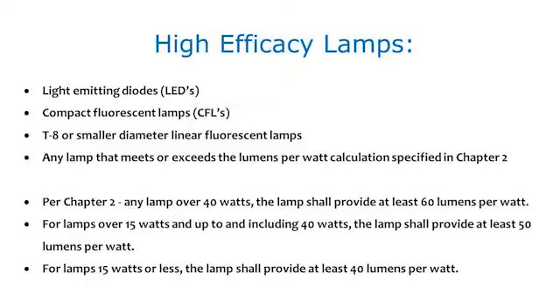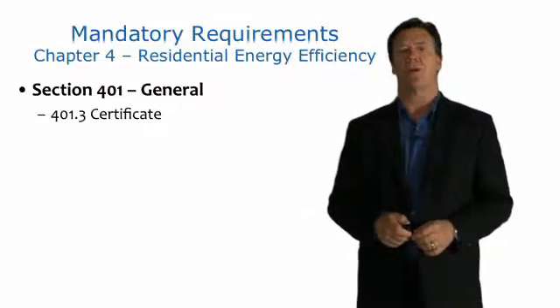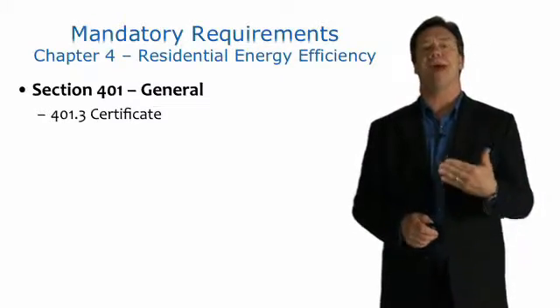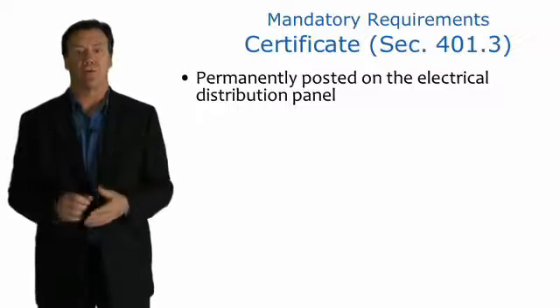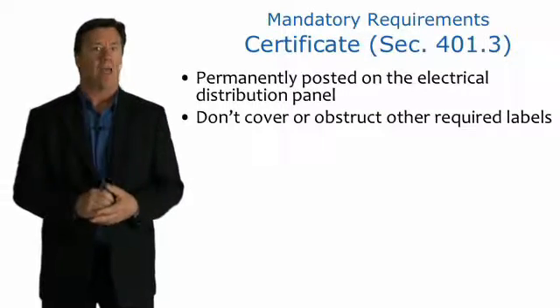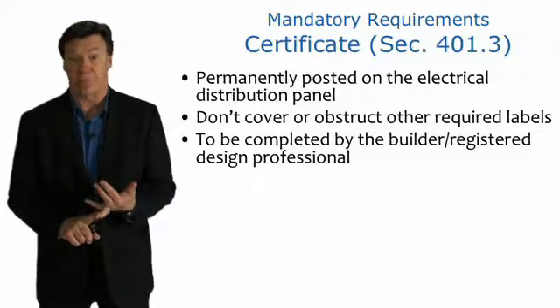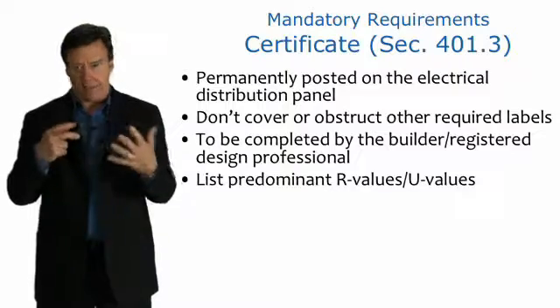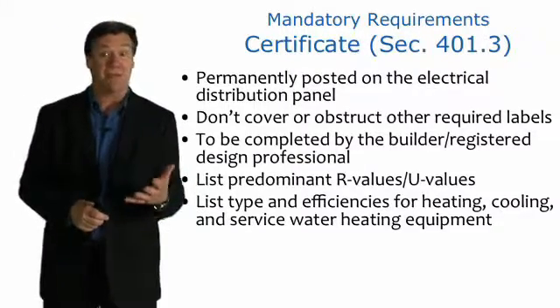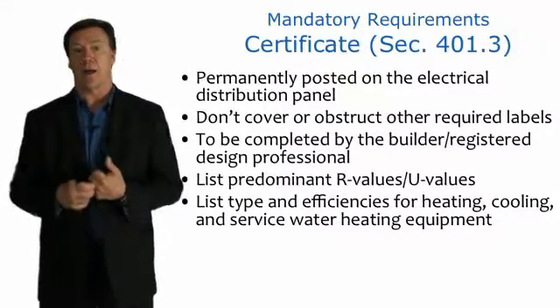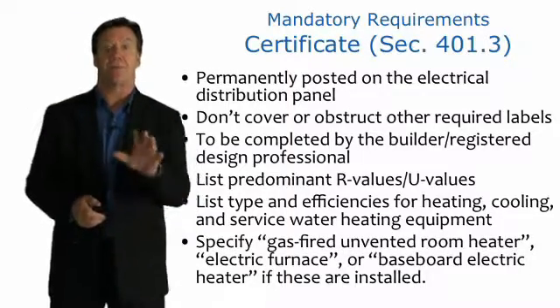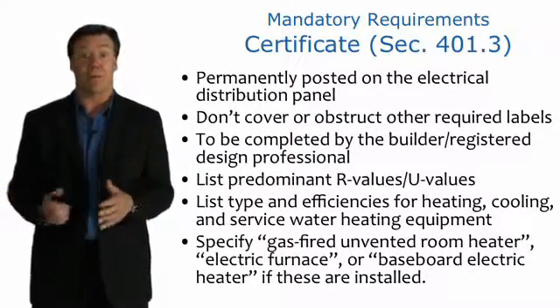High-efficacy lamps are typically LEDs, compact fluorescent lamps (CFLs), T8 or smaller diameter linear fluorescent lamps, or any lamp meeting the code lumen-per-watt requirements. Lumens, in simple terms, means the amount of light produced by a lamp or bulb. Watts is a measure of the amount of electricity consumed to produce that light. So more lumens means brighter light, but to meet the energy code requirements, look for lumens that are produced by lower wattage lamps. Every home must have a certificate permanently mounted to the electrical distribution panel. It cannot cover or obstruct any other required labels and must be completed by the builder or a registered design professional.